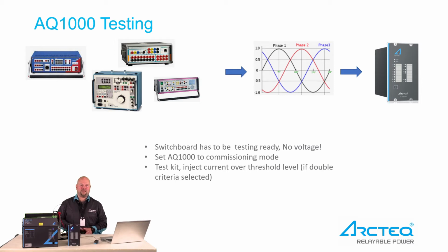What do you need for the testing? Any type of testing kit which can inject 3-phase current to the unit here. This can also work as light only, but if the double criteria, current and light, is selected, then you also need some kind of testing kit for the 3-phase current. It can also be set up with a 1-phase testing kit. It doesn't really matter. You can test 3 phases separately or 1 phase at a time. It is also okay.